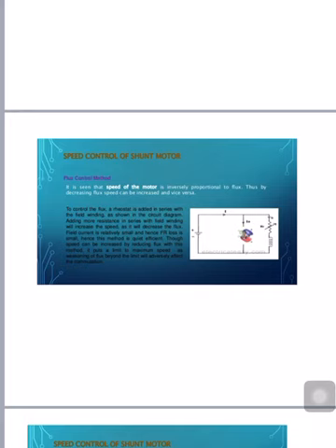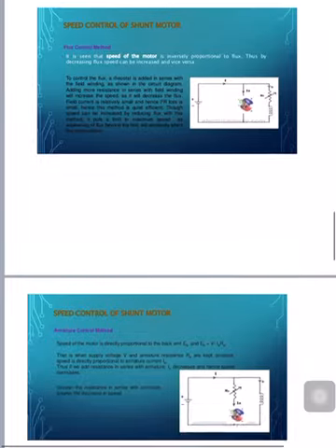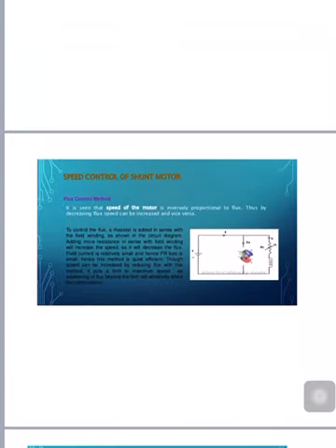That is the speed control of DC shunt motor through the field rheostat method. The disadvantages of this method are that creeping speeds cannot be obtained, and top speeds are only obtained at reduced torque. The speed is maximum at a minimum value of flux, and it is governed by the demagnetizing effect of armature reaction on the field. These are the disadvantages of the flux control method.